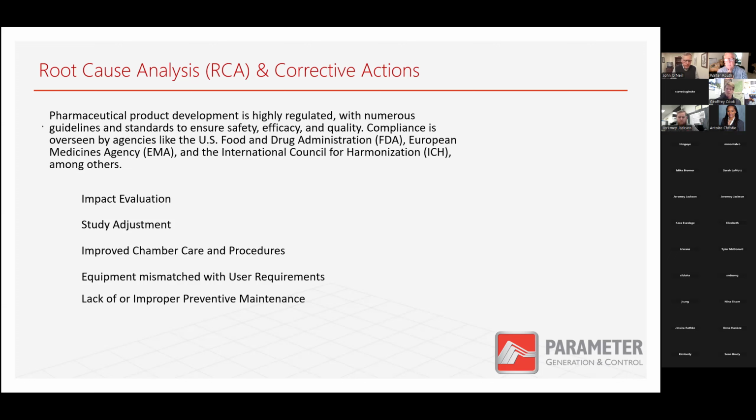That was great. So a temperature dip is one thing. I've also seen alarms where there might be a moisture detector sitting on a shelf or the floor. And if you get a puddle or something, it closes the circuit and sends out an alarm that there's definitely a water condition in there. And that was years ago that we had that kind of technology. I'm thinking by now it must be much more sophisticated, so that you can detect those things a little bit faster than our old-fashioned floor alarms. So hopefully that answers your question that yes, there was an alarm prior to the discovery, and it was the alarm that caused the person to discover it.